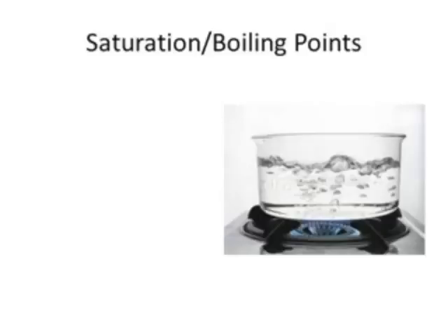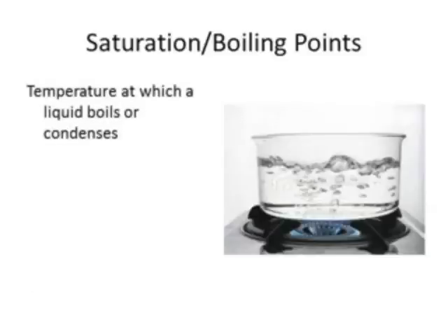The next thing I want to talk about is saturation and boiling points. Basically, this is the point at which a liquid is either going to condense or boil off. When we're talking about a refrigerant, this term is interchangeable depending on what we're talking about. If we're talking about a saturation point, then we're talking about a vapor gas. At what point is it going to condense back to a liquid? Or vice versa, if we're talking about a boiling point, we're talking about what point this liquid refrigerant is going to boil off into a vapor. The point's the same, it's just a difference in terminology in what we're trying to achieve here.